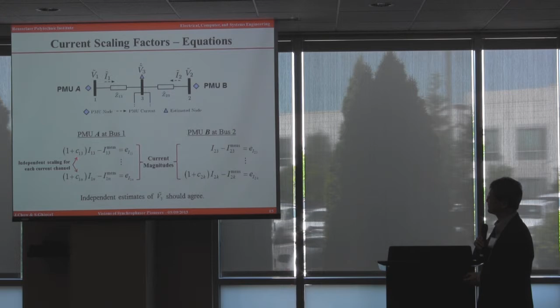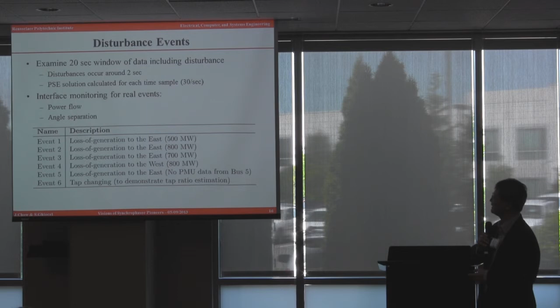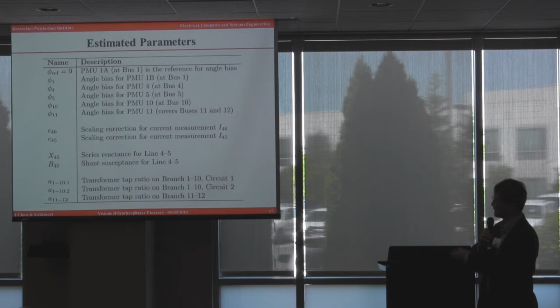We look at a number of events. The really good events to study are loss of generation, 700 to 800 megawatts, where you can see a good signature in the system. And these are the NYPA data, and of course the information we got is from ELU's FNet system, and Dave will help tell us what's going on and so on. So these are the parameters that we can estimate. We estimated the phase bias on 5 of the 6 PMUs; we have to set one of them to be a constant. And some current scaling error that we actually do. You can also now do a line parameter estimation.